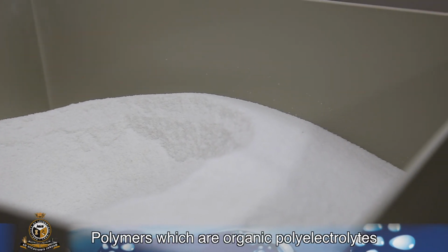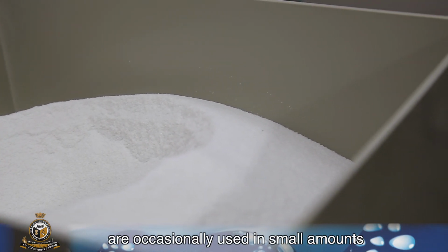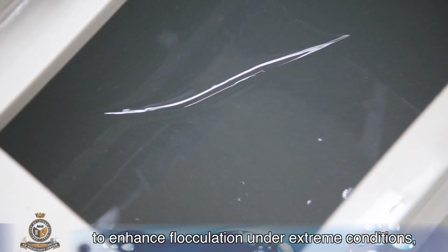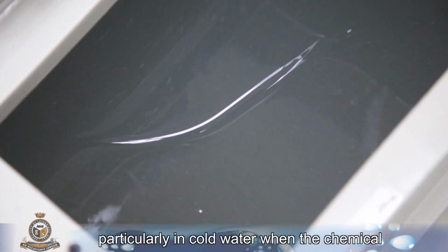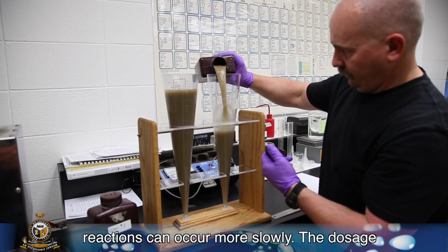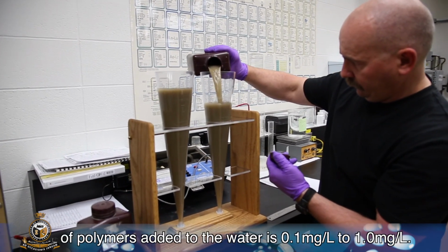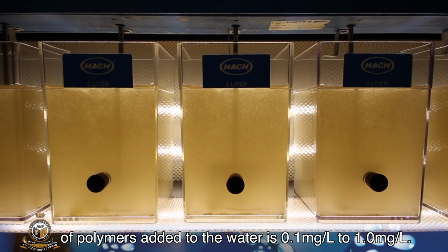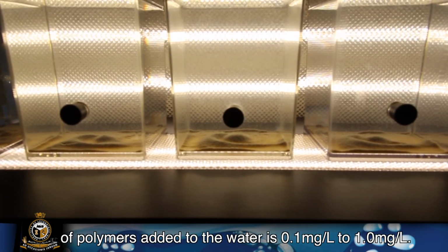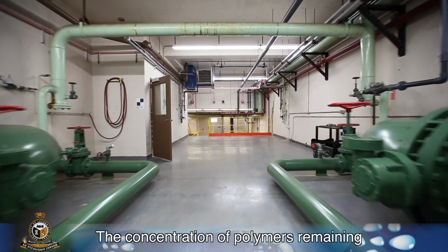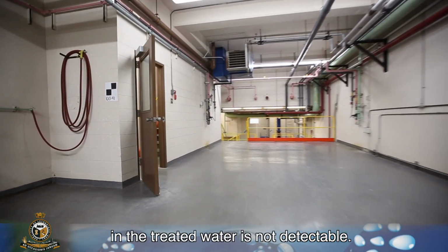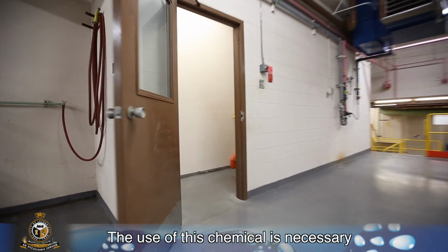Polymers, which are organic polyelectrolytes, are occasionally used in small amounts to enhance flocculation under extreme conditions, particularly in cold water when the chemical reactions can occur more slowly. The dosage of polymers added to the water is 0.1 milligrams per liter to 1.0 milligrams per liter. The concentration of polymers remaining in the treated water is not detectable. The use of this chemical is necessary to produce potable, quality water.